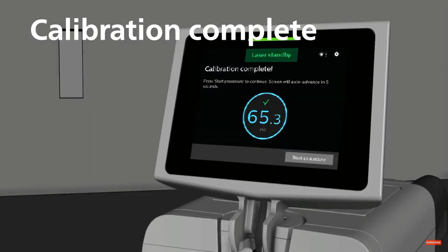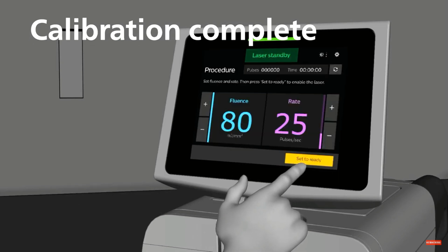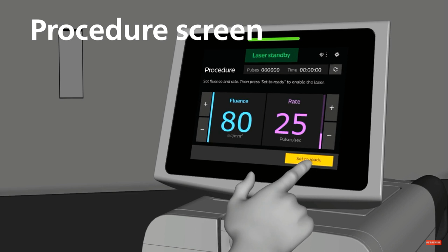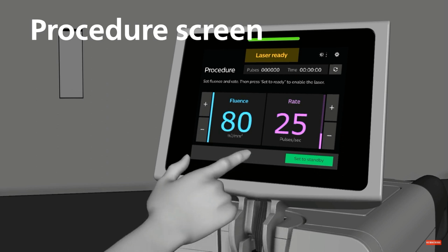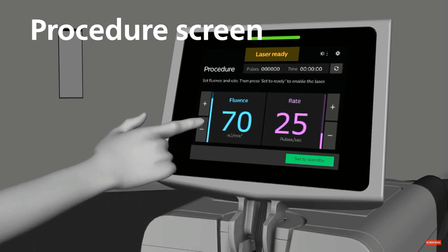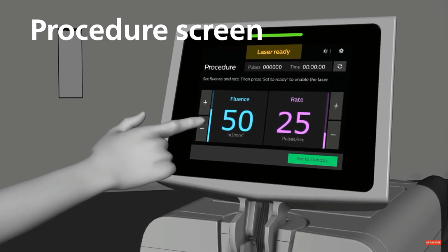The system will auto-advance to the procedure screen in 5 seconds. This may be bypassed by pressing Start Procedure button. Pressing the Set to Ready button places the system in Ready mode. If the system has not been calibrated, the system cannot enter the procedure screen. Fluence and rate settings are adjustable based on procedural need and physician's discretion. To adjust settings during the procedure, please use the interface of the procedure screen.